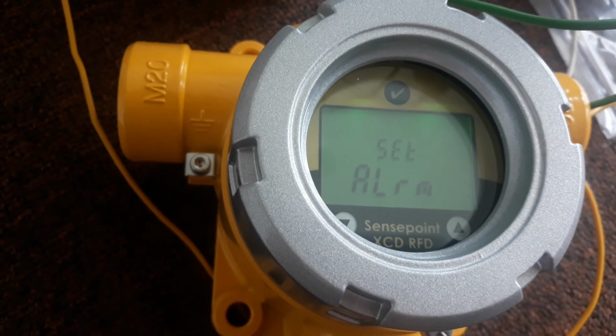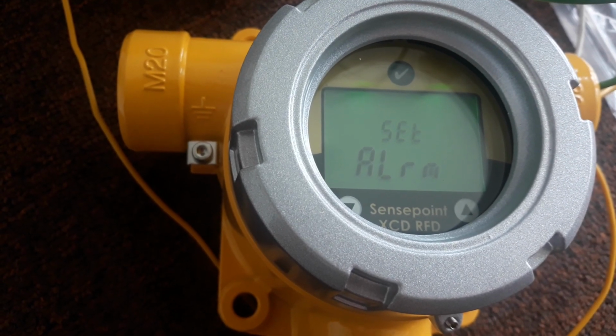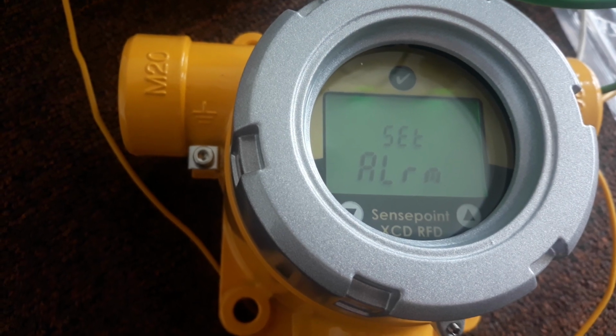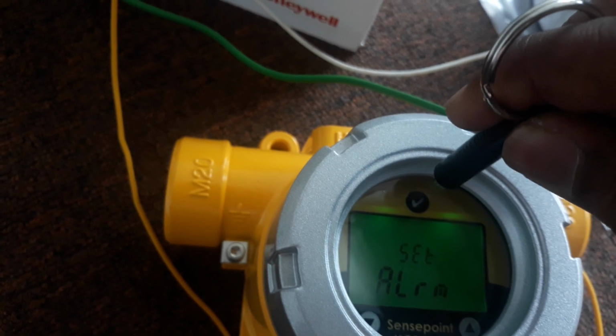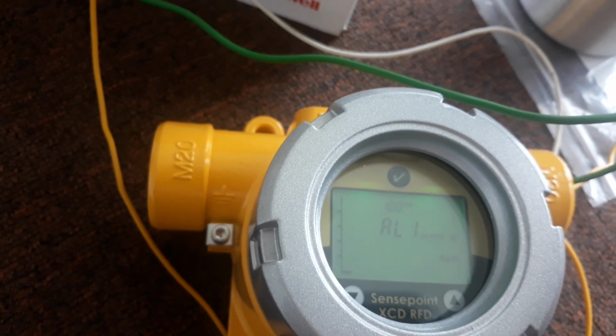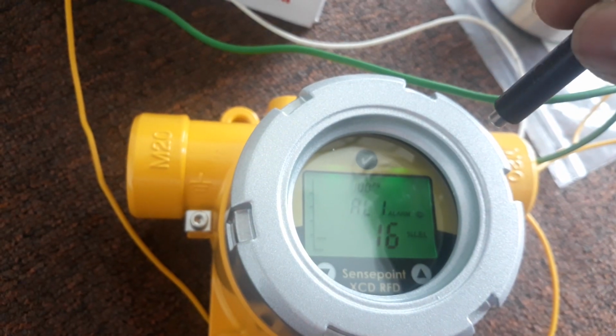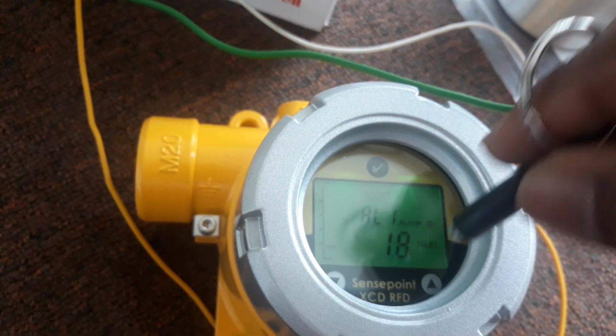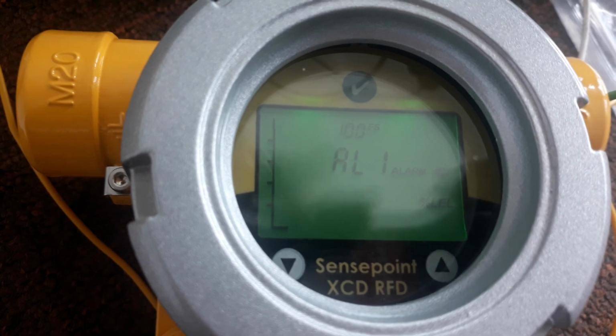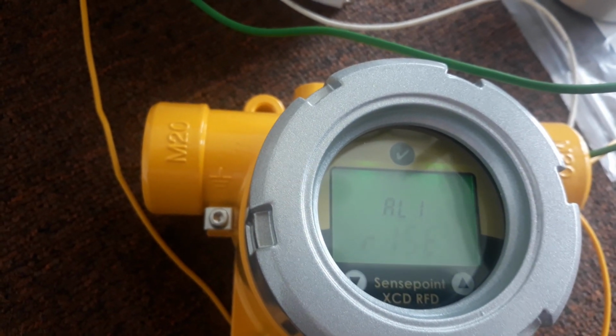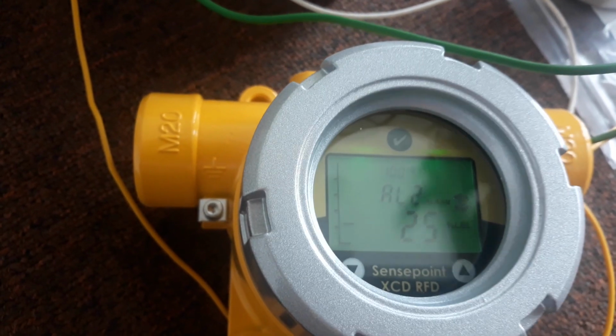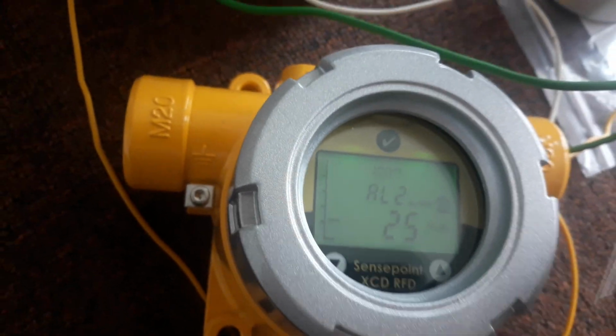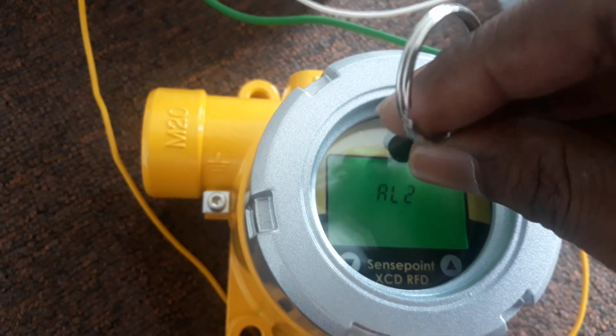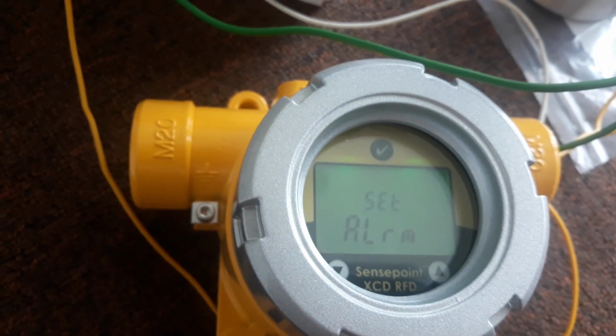Okay, this one is for setting the alarm. Normally you can get the values from the supplier: first alarm is 20 and second alarm is 40. If we want to set the alarm, you can touch the right button and change it. Let's say I want 20. Okay, you see, my first alarm is 20. Then push the right button. So my second alarm is 25. Okay, set alarm is done.